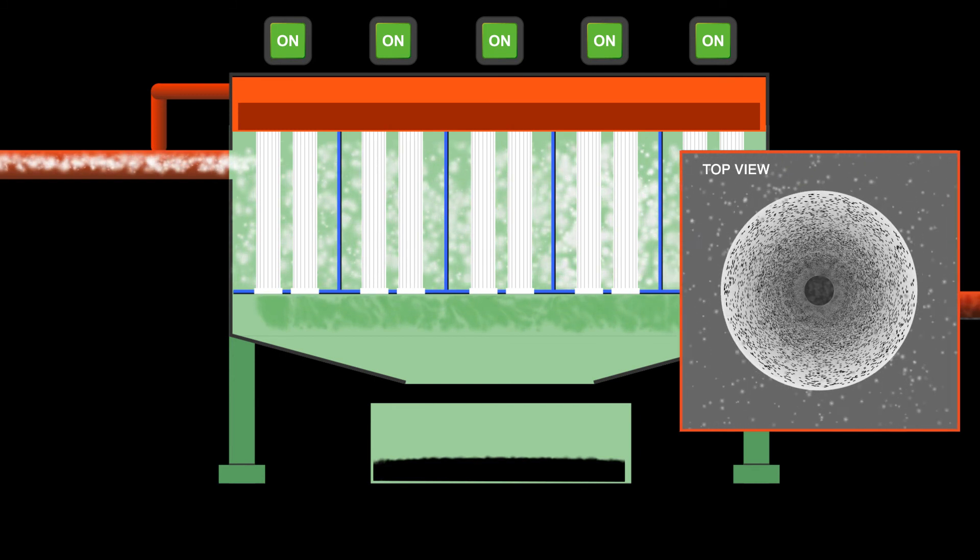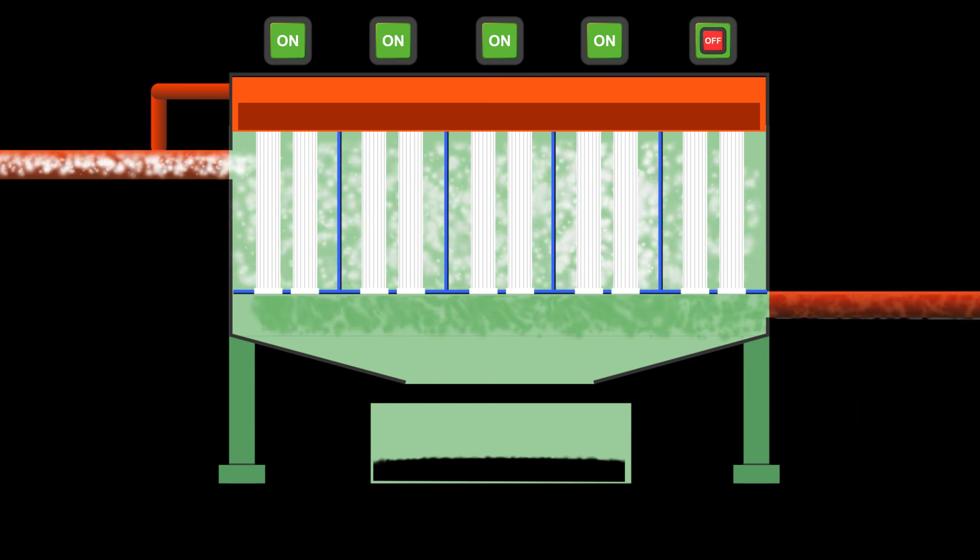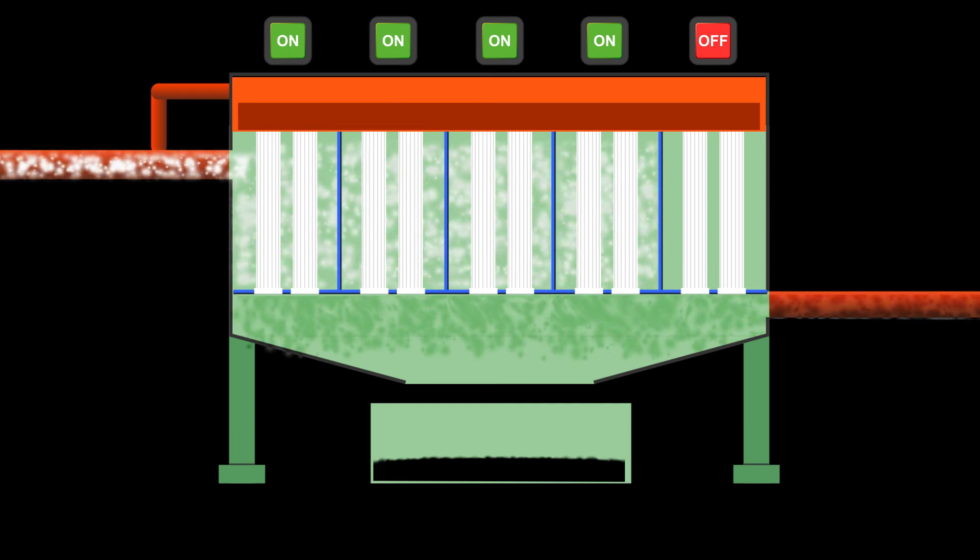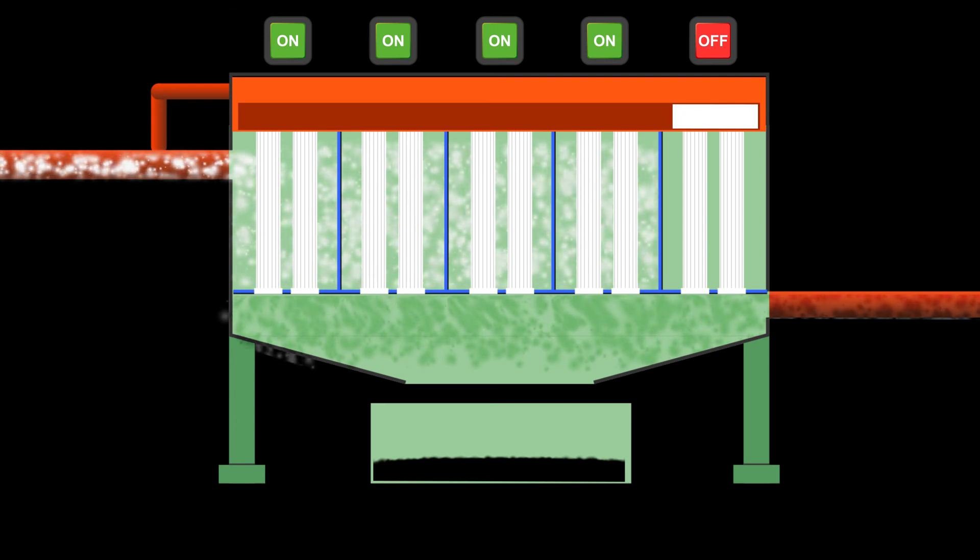These types of reverse air baghouses have to be taken offline for cleaning. Thus they are often divided into compartments so one section at a time can be cleaned. Generally, an entire compartment is pressurized with a system fan in the reverse direction of filtration.